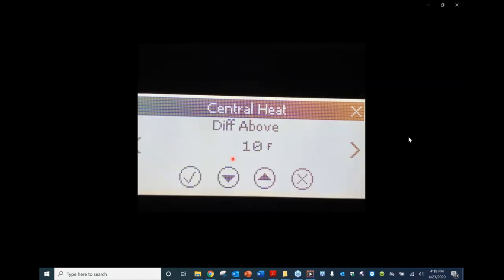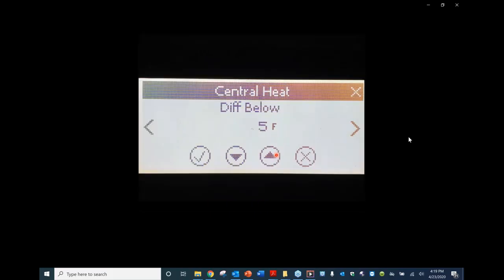Our diff above is when the burner will turn off. Our set point's 170, the burner will turn off at 180, 10 degrees above 170. Our diff below is when the burner will turn back on. Turns off at 180, 5 degrees below 170 is 165. The burner will turn back on at 165.